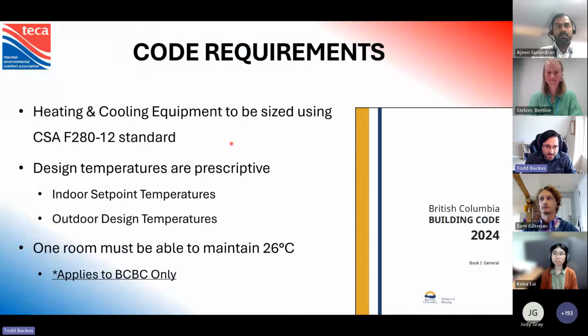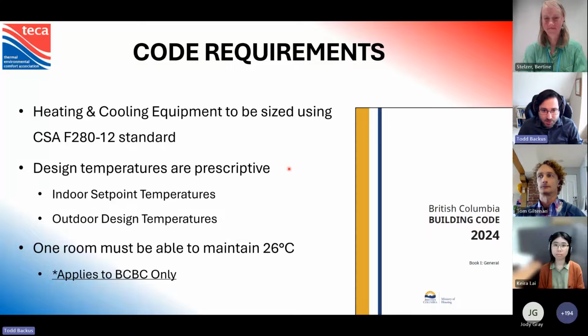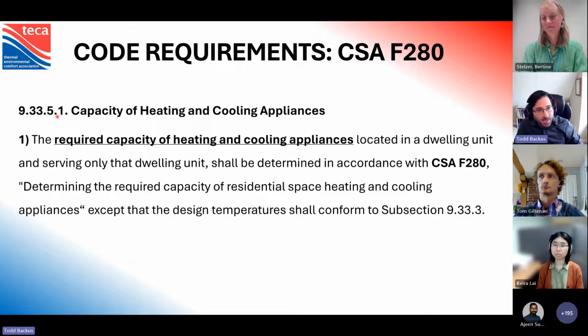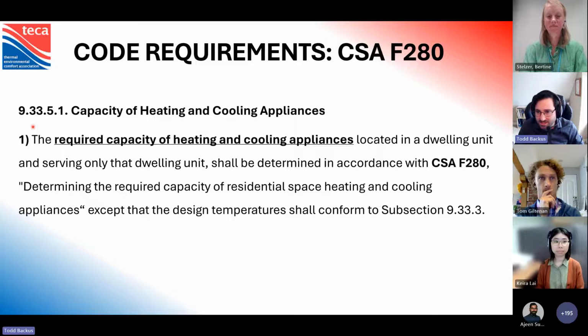Heating and cooling equipment is to be sized using the CSA F280 standard. The design temperatures are prescriptive and outlined in the code. And then in the BCBC only, there is this refuge room, the ability to maintain 26 degrees C. It's my understanding that this will, in the next cycle, apply to the National Building Code as well, but currently it's only in the BCBC. So this is the actual sentence from the code under 9.33.5.1. The required capacity of heating and cooling appliances located in a dwelling unit and serving only that dwelling unit shall be determined in accordance with CSA F280, except that the design temperature shall conform to section 9.33.3. So this was added in the last code cycle, and cooling appliances. Previously, this line only mentioned heating capacity, but now we're asking for heating and cooling appliances.